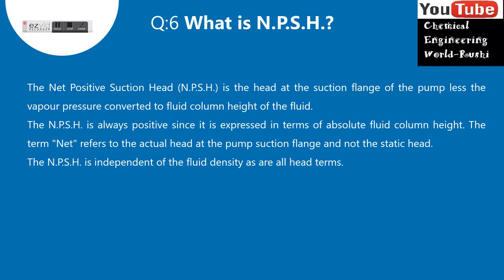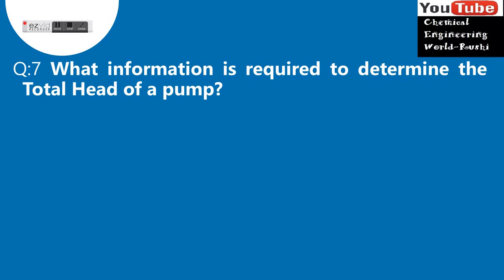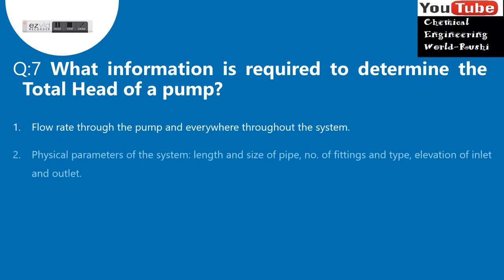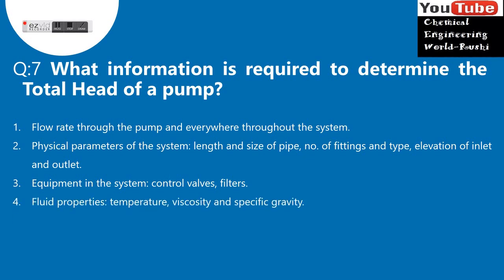Question 7: What information is required to determine the total head of a pump? 1. Flow rate through the pump and everywhere throughout the system. 2. Physical parameters of the system: length and size of pipe, number of fittings and type, elevation of inlet and outlet. 3. Equipment in the system: control valves, filters. 4. Fluid properties: temperature, viscosity, and specific gravity.